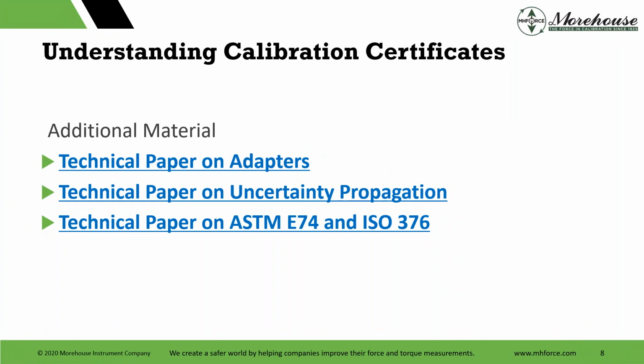We also have some additional material. This presentation is available in PDF, and we have a technical paper on adapters, highly recommended. You can get everything right, but if you don't use the same adapter, the output or the deflection is different, and then you can't replicate what we do in our lab. We do a calibration, and we give you the expected performance of that device at the time of calibration. Now, as the end user, you would go and derate that. You would use it at different temperatures, in different conditions, on machines that are not as plumb, level, square, and rigid. So it is really important to get the adapters right, because they will change the deflection. They can change the line of force, and not getting them right can result in really large measurement errors of up to probably 0.5% on some different cells and adapters.